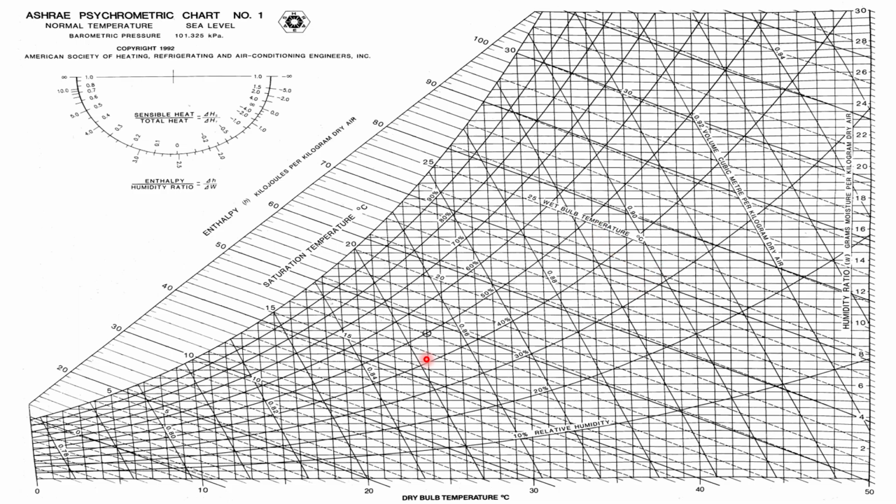This is again a psychrometric chart, and this is my reference point from where we will plot different processes. If I extend this line in a leftward direction, you can see my temperature is decreasing, but my humidity ratio or specific humidity is constant. This process is called cooling or sensible cooling. Exactly reverse to that, if my process happens in this direction, again my humidity ratio is constant but temperature is increasing, then this process is called sensible heating.